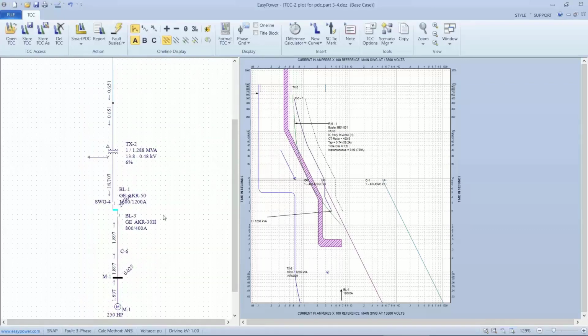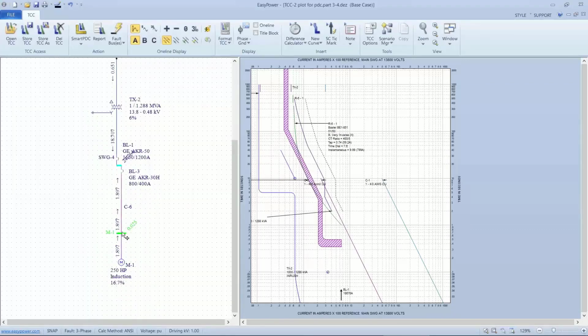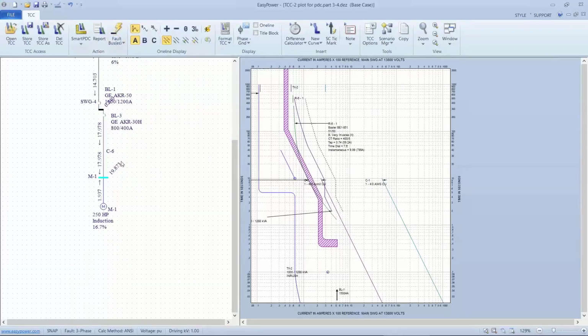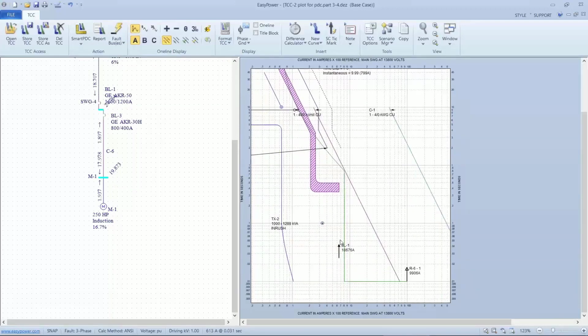Okay, so yeah, the instantaneous is set up on this relay, and the reason it doesn't show up is that the set point is above the max current that we'll see for a downstream fault. If I click in an open area and fault all the buses, I can see my instantaneous is set greater than BL1 will ever see, and BL3. So there's no coordination issues even though I have an instantaneous element set. Fair enough? So if I get a fault downstream, it won't even show up on my curve.